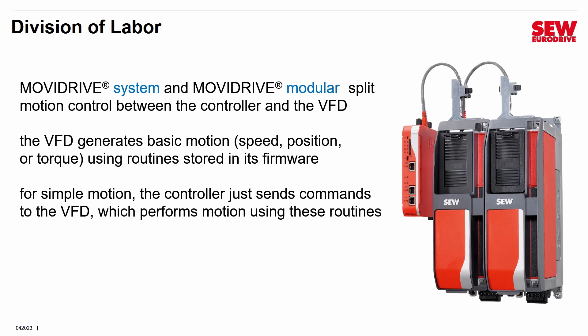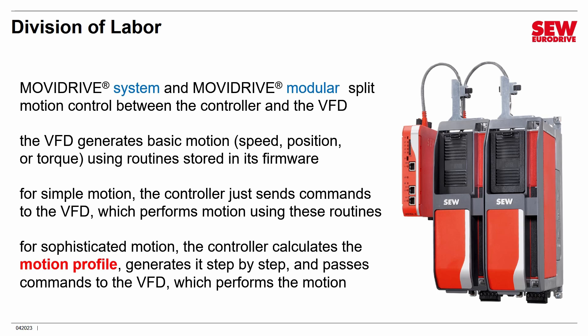You don't need a very big controller if your VFDs are mostly doing simple motion. But if you want to do something really complicated like a camming application or a robot, then the controller has to do a lot more work. It's calculating step-by-step a motion profile, and then passing commands to the VFD — giving it little baby steps telling it what to do. The VFD uses its firmware to carry out those baby steps, but the controller is doing a lot of work calculating all those baby steps second by second. That is really the key difference between Movidrive System/Modular and Movidrive Technology.